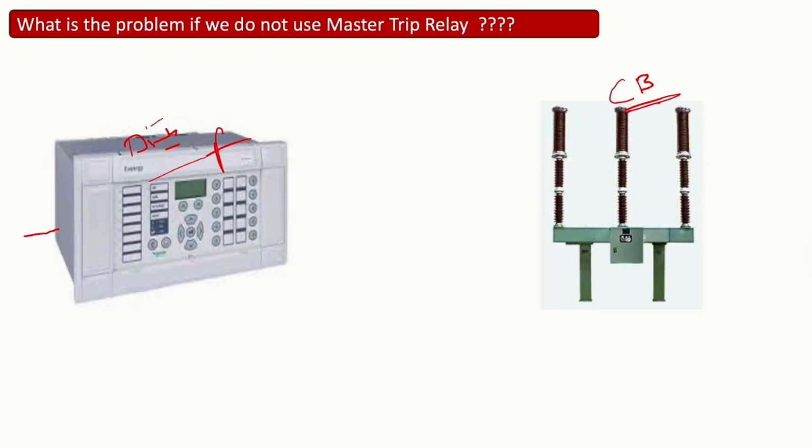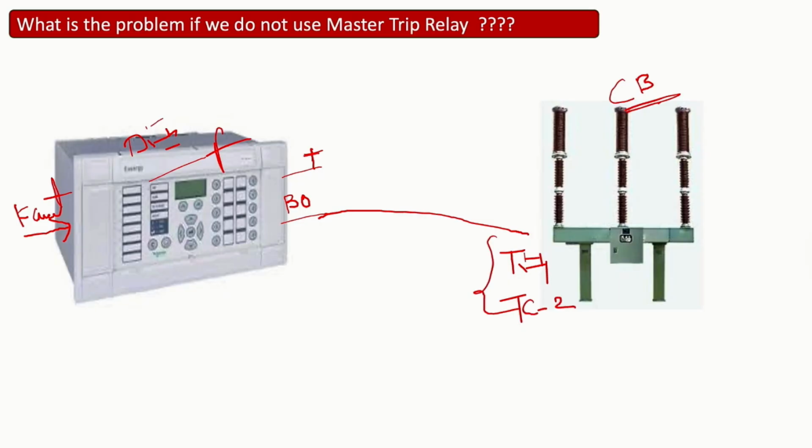What happens now is that when it trips, the negative current passes through the relay. Okay? And this relay's BO, which we call the binary output, is positive on one side. The second wire goes directly to the breaker's tripping coil, either TC1 or TC2. When the relay operates, the BO will be high, so this positive here, this contact will be NO, so it will latch, and this positive will transfer here, tripping our TC2 trip coil, and this breaker will trip. This is a simple phenomenon.